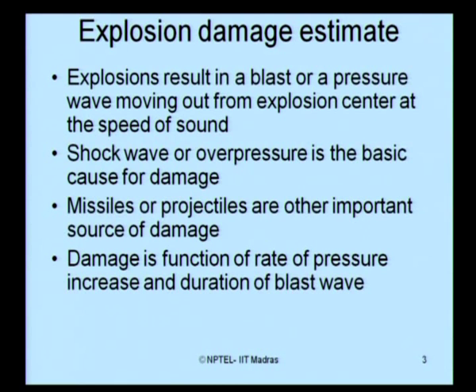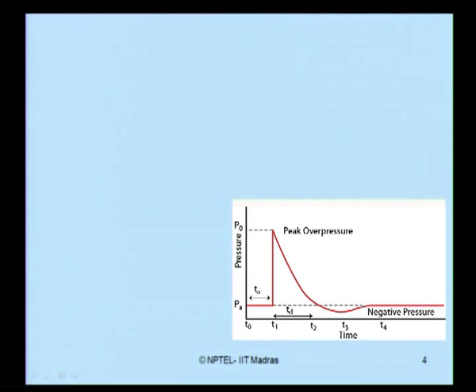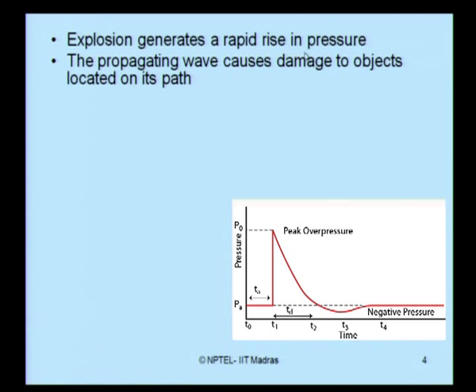Blast damage is estimated based on the peak side-on overpressure. To estimate explosion damage, one should understand the rate of pressure increase and the duration of the blast wave. Looking at a pressure-versus-time figure, the explosion generates a rapid rise in pressure. Before the pressure overshoots to its peak value, there is always a time delay called arrival time. Once the pressure reaches its peak value, P-naught or peak overpressure, practically within no instant of time, the pressure rises from atmospheric to the overpressure.